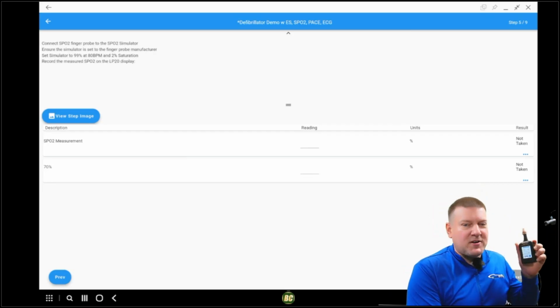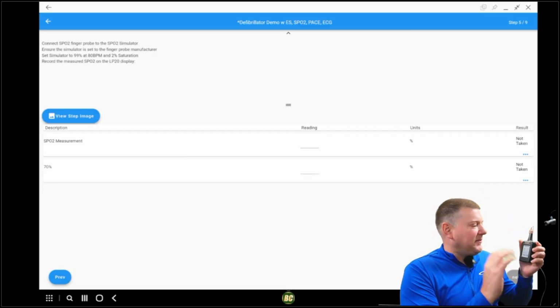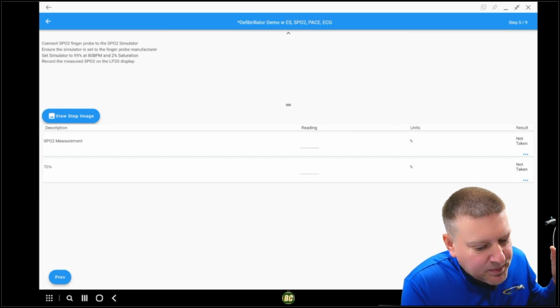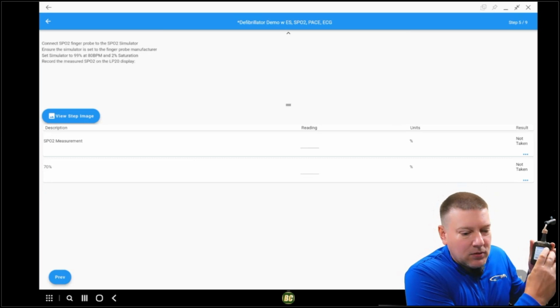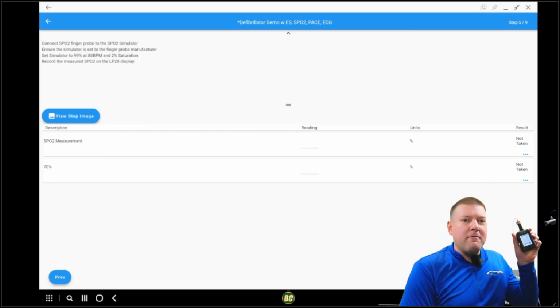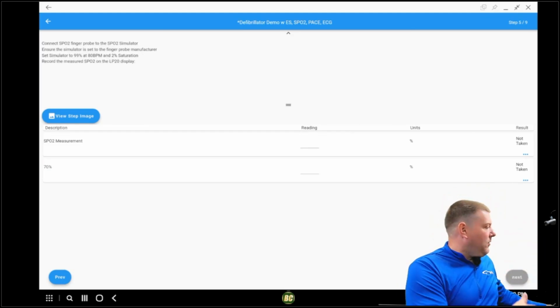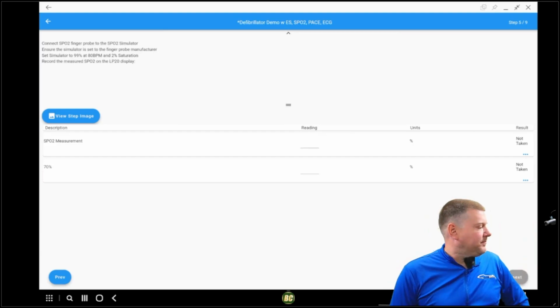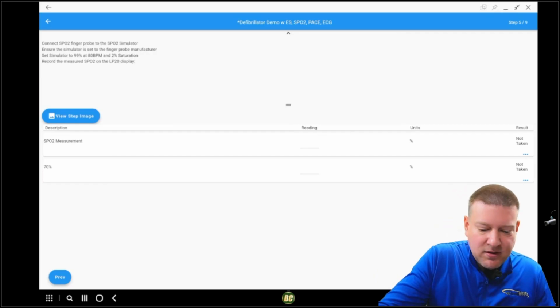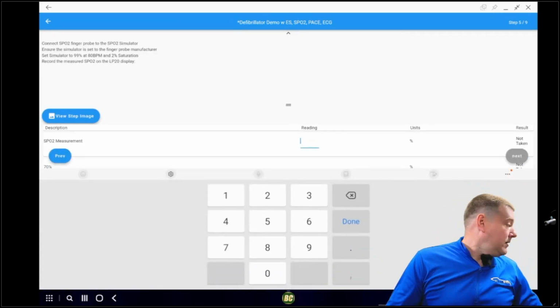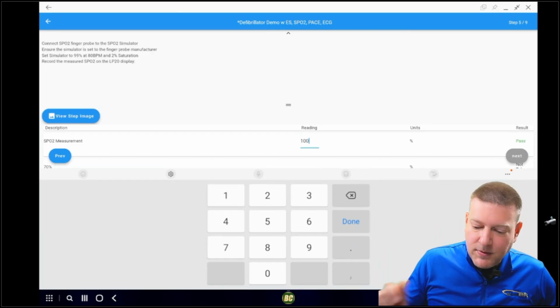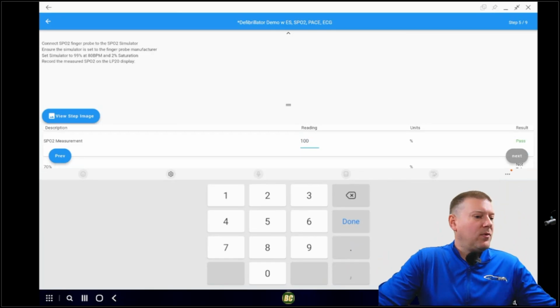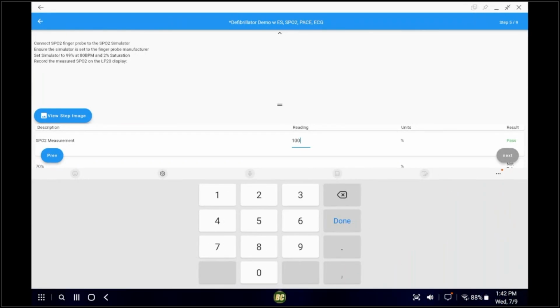Guys, you gotta love these touchscreens. I love touchscreen test equipment. Okay, and it says 2% saturation at 80 BPM. There we are. That easy. And now I look over at my screen and it will register an SpO2. I'm looking for 99%. Oh, it's at 100. And notice that right over here, it shows a green pass condition on the side. So that test is passed.